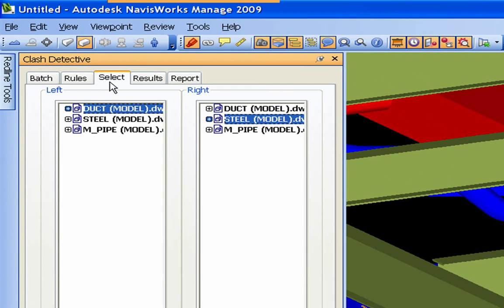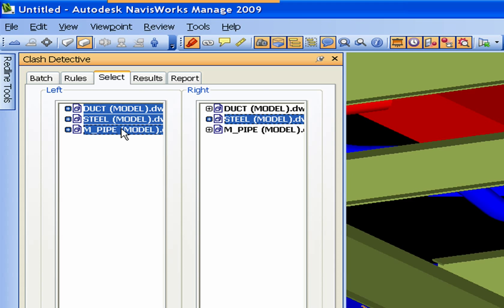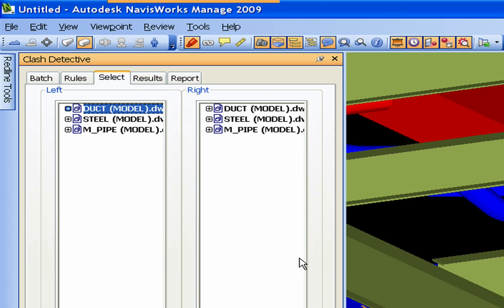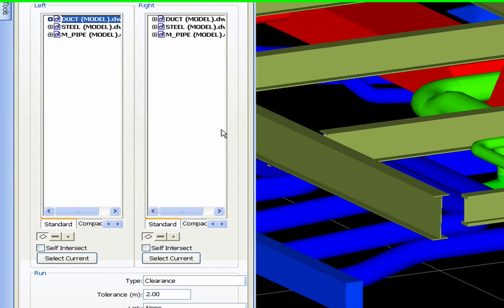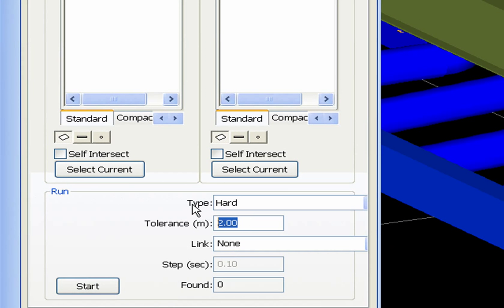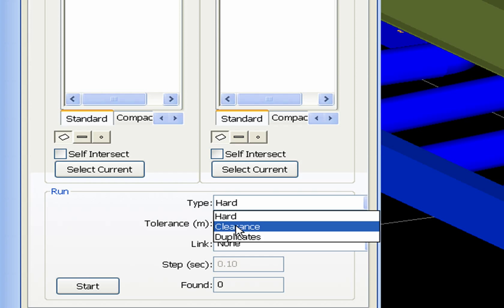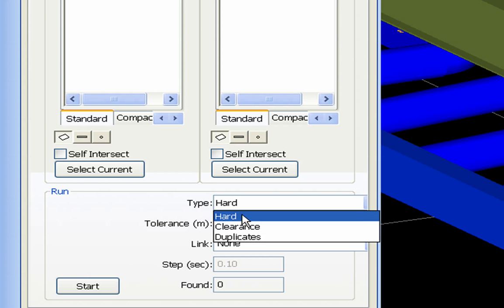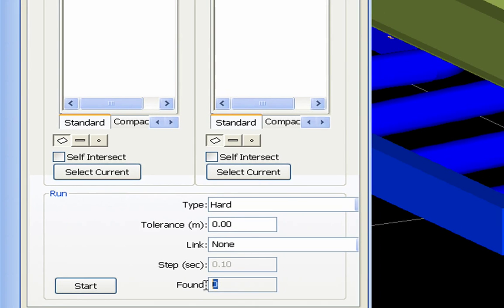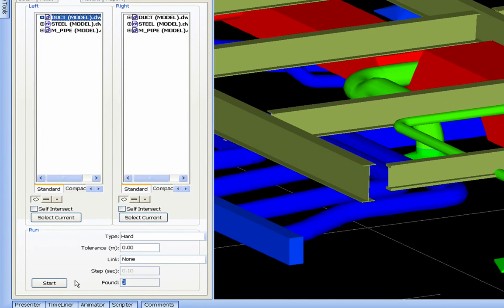The select tab is basically what we went over the other day. You can select more than one with the shift or control key and run it against that. We'll start with the duct and the steel. Down here is where you're going to set this. We'll set it to hard and zero, but you can run it to clearance and then set it to whatever inches you want. Link - I'm not sure what that does. And this is your found, this is your results. So we'll go ahead and restart it, and we found 21.